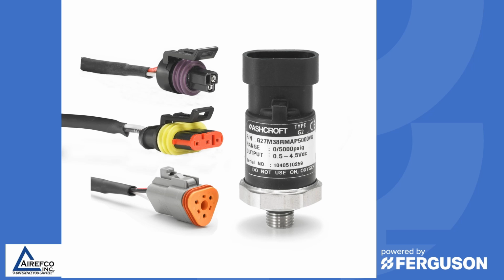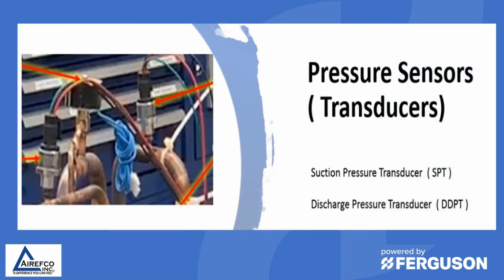There are a variety of different kinds of plugs that plug into transducers to relay the signal back to the control board. When troubleshooting a transducer, the first thing you want to do is make sure that the plug is properly seated in the back of the transducer and it's sending the proper voltage to the board to relate the pressure. So on most residential heat pumps and air conditioners, you're going to find two pressure transducers, a suction pressure transducer and a discharge pressure transducer.